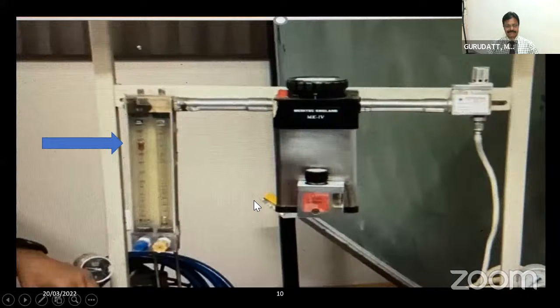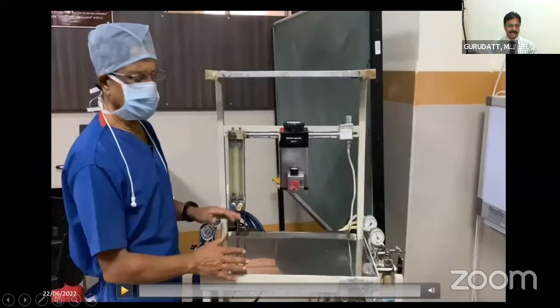Here in this machine, there is a master and slave mechanism. I'm not giving any oxygen, but still you can give nitrous oxide provided the oxygen pressure is there inside. I have opened the oxygen either pipeline or the cylinder. Then as long as the oxygen pressure is there, I can still give only nitrous oxide through the flow meters. So I'll just demonstrate this. Many times you'll be asked to demonstrate this master and slave mechanism in the exam. I'll show you a video of how the master and slave mechanism will work.